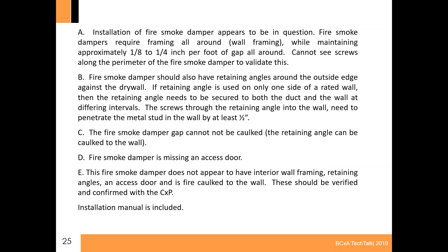Here we've got retaining angles around the life safety damper, screwed into both the sleeve and the wall, with retaining angles on both sides of the wall. The requirement is that if you're on both sides of the wall, you can only screw into the sleeve, not the wall. On a shaft wall where you don't have access to the inside, you can screw into both the sleeve and the wall as long as your screw spacing is appropriate.